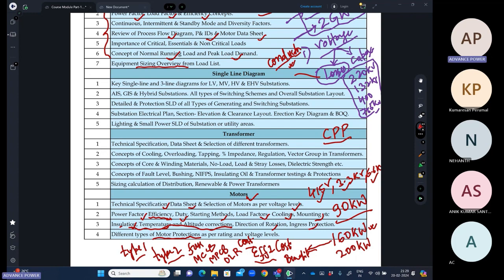Then we'll go for ACB fed motors. We'll discuss the overloading of the motors, thermal overloading, negative phase sequence. Then we'll discuss the overcurrent and earth fault protections for higher rated motors. And further, when the motor is more than 1 megawatt, we also use differential protection. In detail we'll discuss all those protections also.